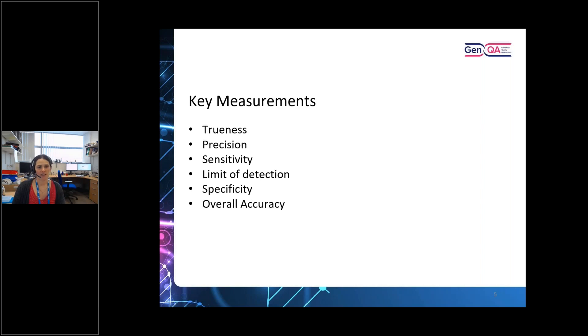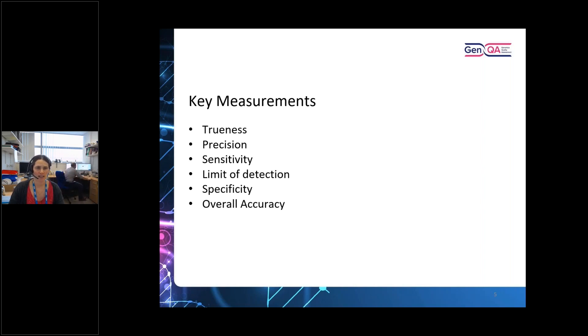Once you've got all the background information of the test you're trying to run, there are a number of considerations around the technology. From the technology point of view, you need to be looking at the results it gives and some key measurements. The first is trueness — how close the results are to a reference value. If you ran the test multiple times, you'd have an average of that result. What is the variation from that average? Do you get any outliers? And it's linked to precision — so precision is how much it varies, often expressed as a clinical confidence interval from your mean. You need to understand the full range of results and what they mean.